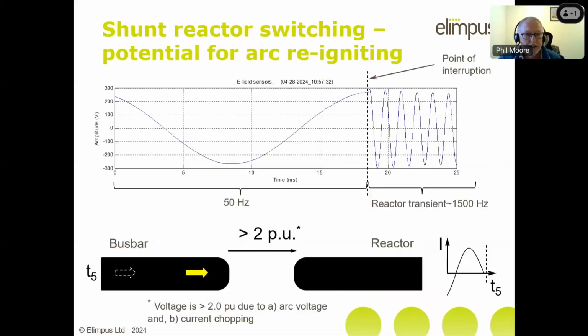Let me try and explain that. What we're looking at here is the terminal voltage, this blue trace here, the terminal voltage of the shunt reactor. Before the arc goes out, we have a 50 Hertz signal, and then at this vertical dotted line, this is the point of interruption. This is voltage, so the voltage is at its peak there, and the current will be at a zero crossing. So the current goes out, and we then go into this very high frequency transient, and that's caused by, as the arc goes out, you can see the current is at a maximum.